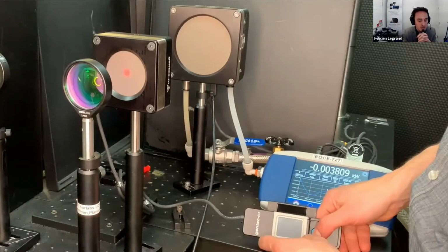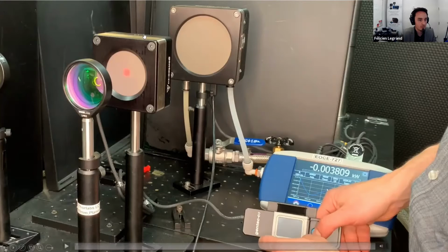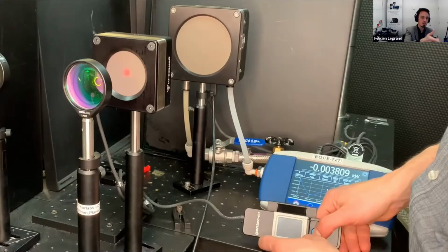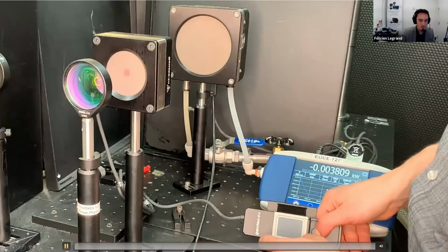And you'll see that a good guideline is to use between 50 and 70% of the surface of the absorber. It could be smaller than that, thanks to the high damage threshold, but it's a good habit for good repeatability. So the first detector we have in the beam path after the expander is a Pronto 10K. This one takes up to 10,000 watts, but for 5 seconds max. The same kind of technology I showed you earlier with the welder. So let me show you how we set this device.